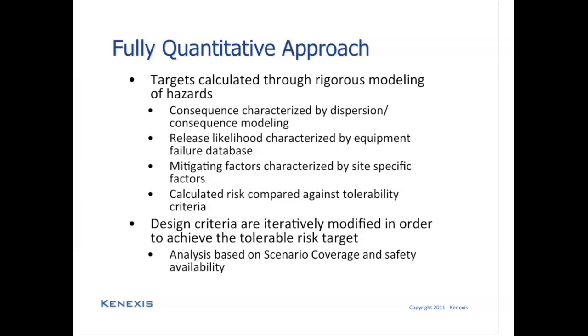But if it is determined that the existing risk is not tolerable, some sort of design needs to be made. Some sort of recommendations for a fire and gas system design needs to be made to reduce the overall level of risk. Now, once the preliminary fire and gas system design has been put in place, all of those consequence scenarios and release scenarios that were defined are going to need to be considered using the scenario coverage technique and the calculation of safety availability to determine what is the beneficial effect that the fire and gas system has on achieving the overall tolerability of risk target.